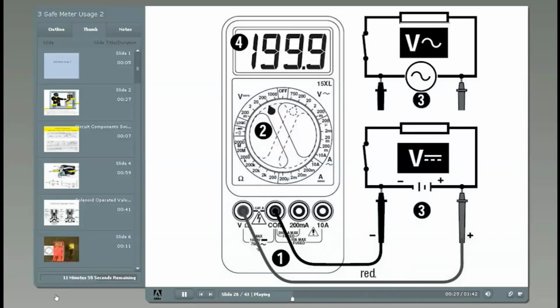To measure voltage, the voltmeter test leads are connected across 2 points of potential difference. This measurement is taken in parallel with the component being tested. With the meter leads in their proper location on the meter and the manual range properly set to a higher range than that expected to be measured, connect the meter in parallel with the component being tested. Apply power to the circuit and reduce the range of the meter so that a reading cannot be obtained, and then move it up 1 range.